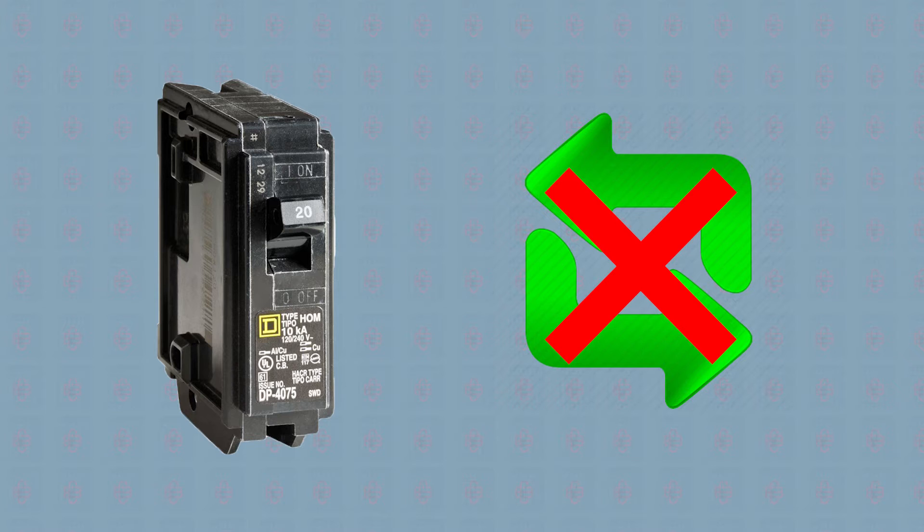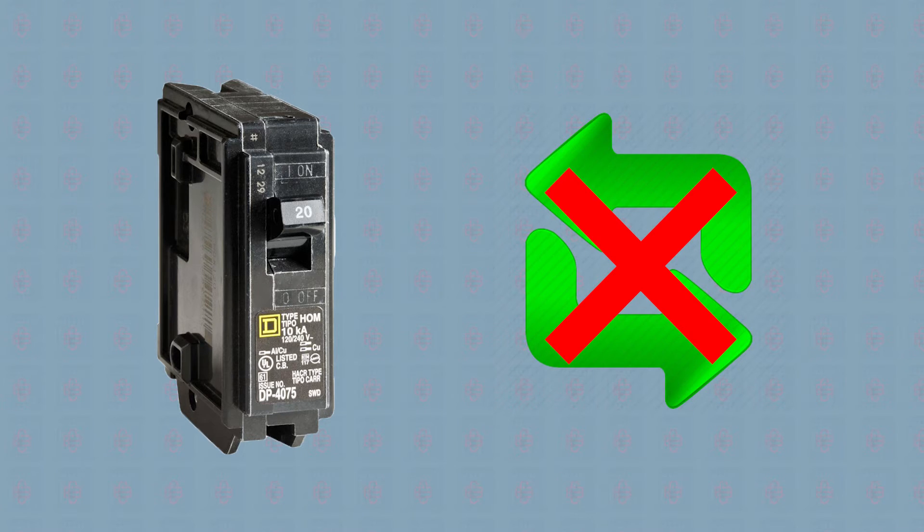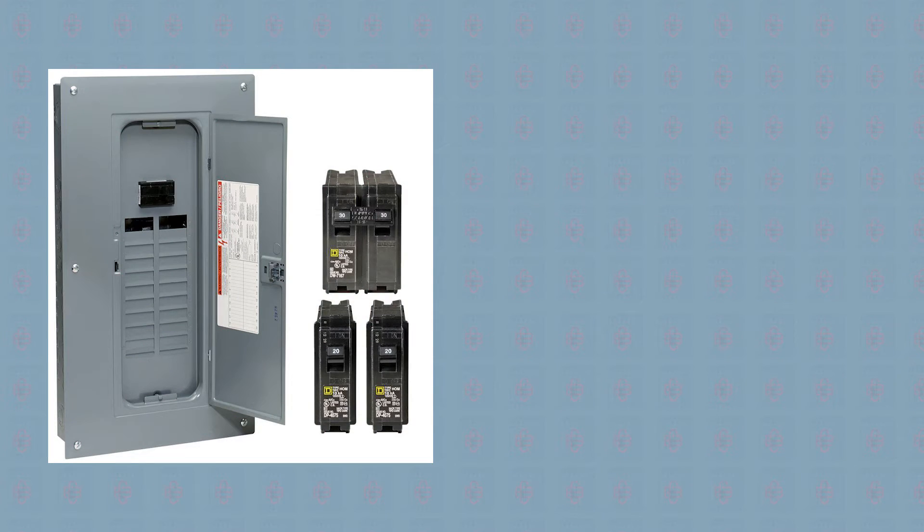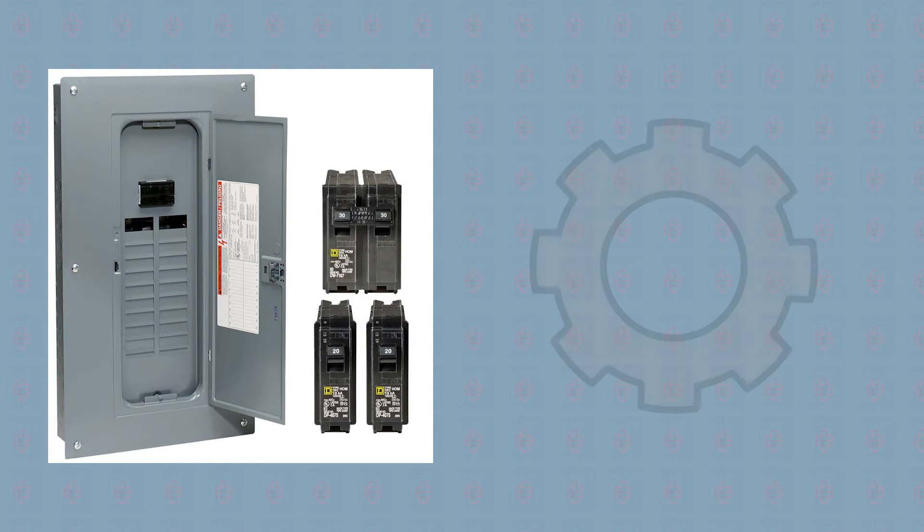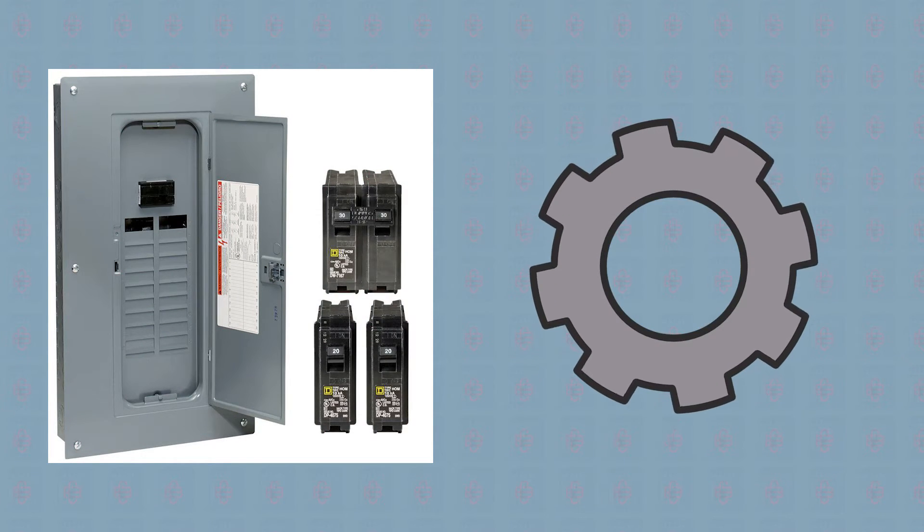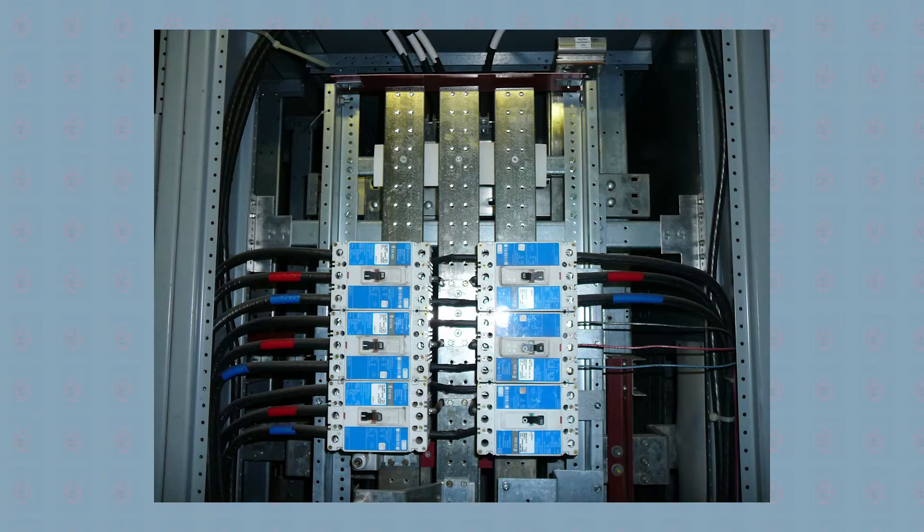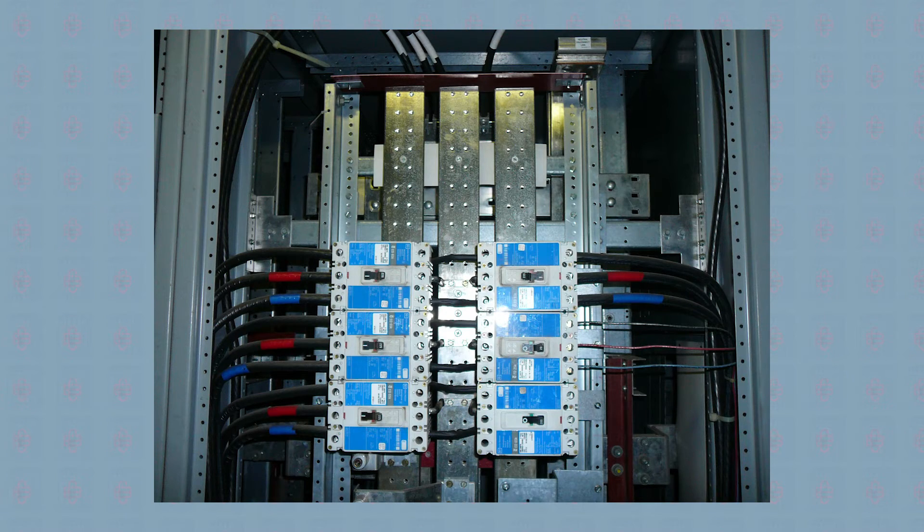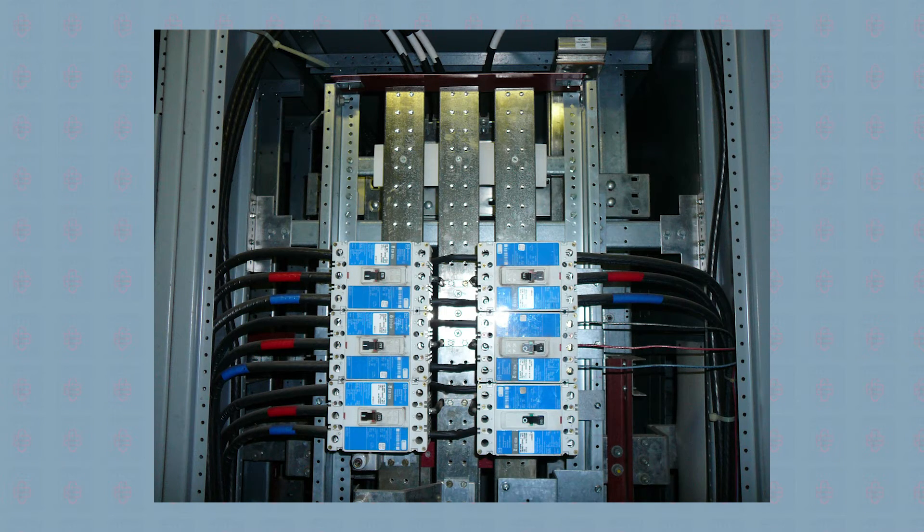Others don't serve the correct purpose even if they're technically compatible. Physical differences between breakers and panels are also rooted in functionality. For example, bolt-on mounting is typically essential for industrial panels due to factors like vibration and panel scope. In this instance, you wouldn't be able to use a snap-in style breaker.